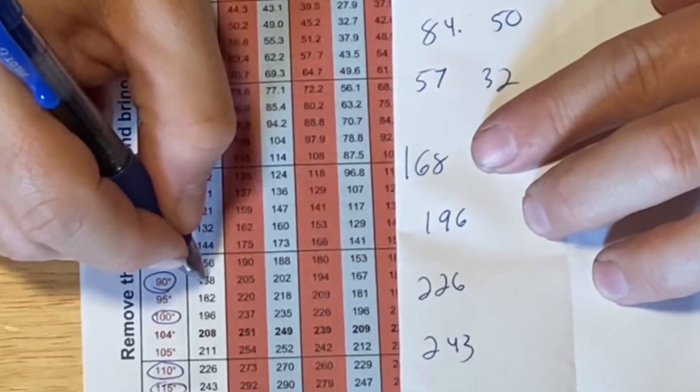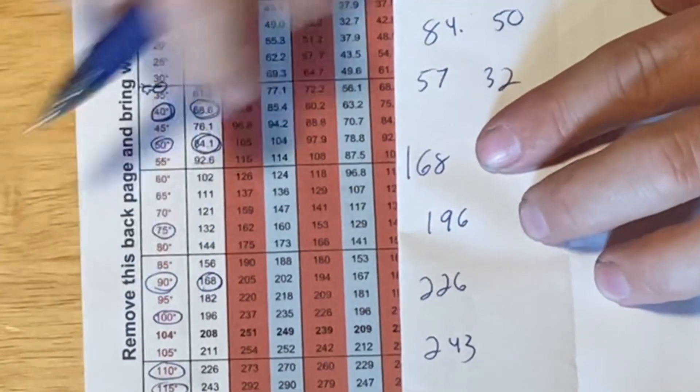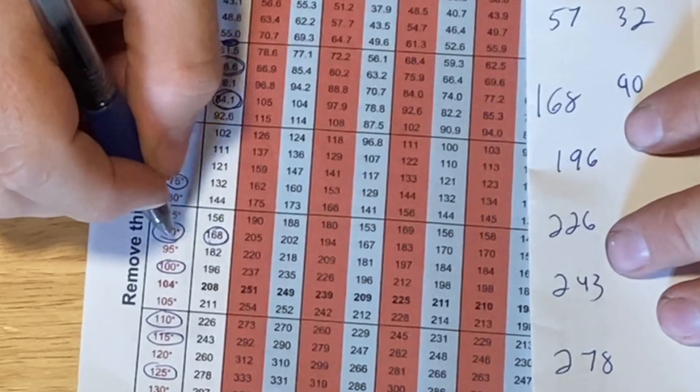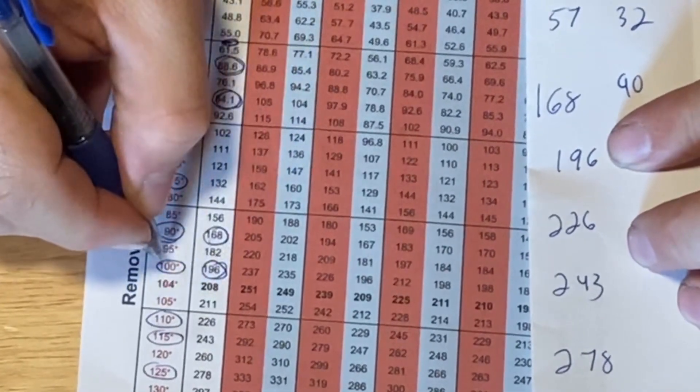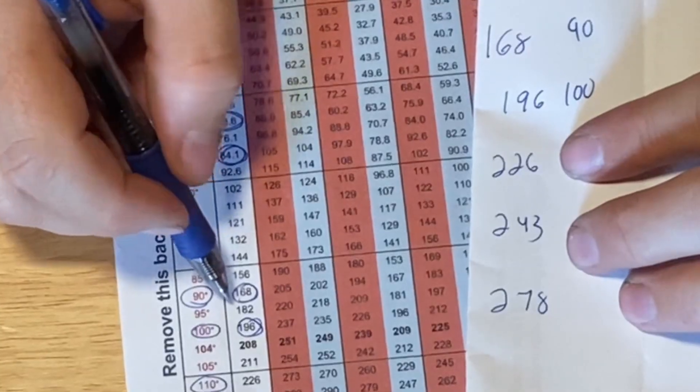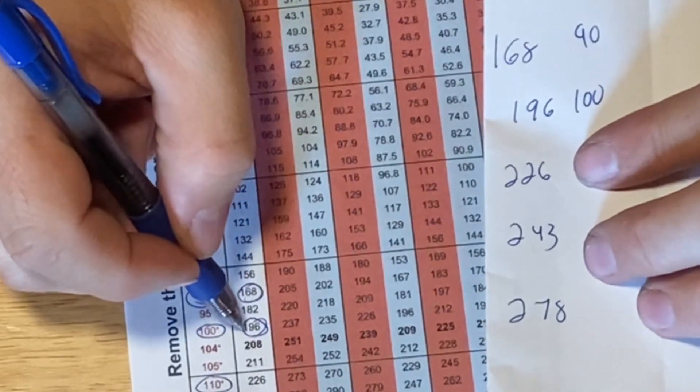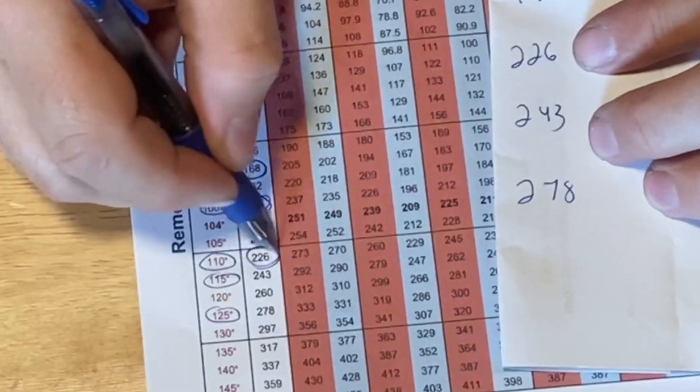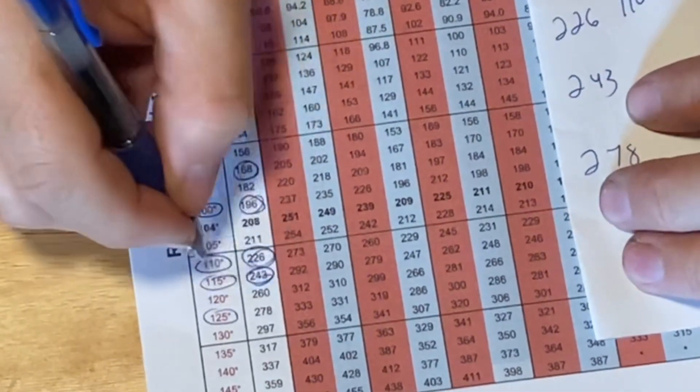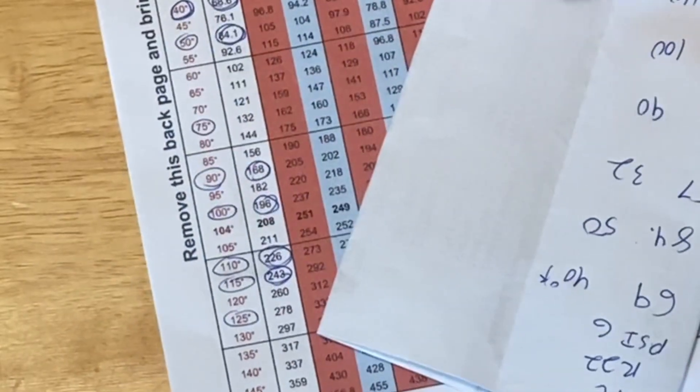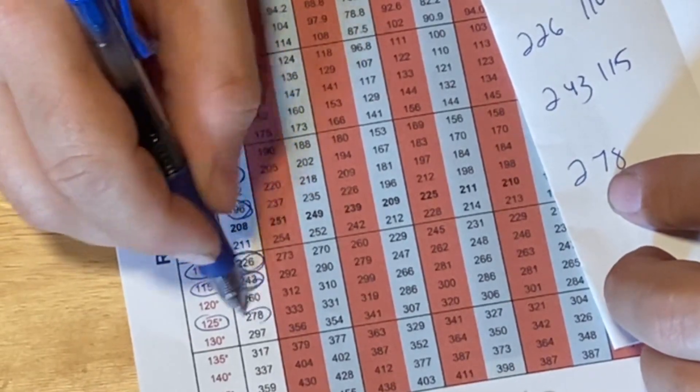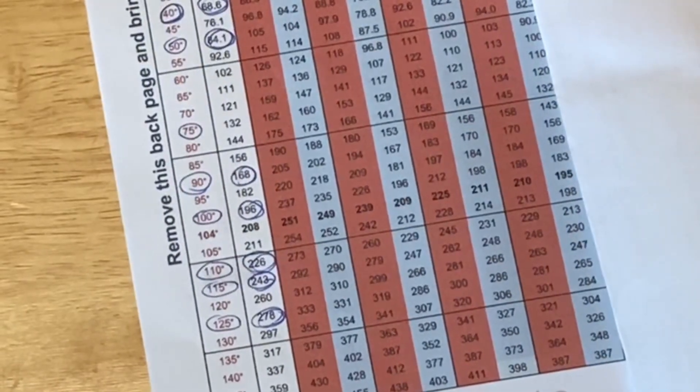Next on the list we have 168. So this could be the high side the red gauge. 168 converts to a saturated temperature of 90 degrees Fahrenheit. 90 would be warmer than the air temperature outside. So we have another temperature of 196. 196 converts to a saturated temperature of 100 degrees Fahrenheit. Now we have 226. That converts to a saturated temperature of 110. And we have 243 converts to a saturated temperature of 115. And then we have our pressure of 278 converts to a saturated temperature of 125 degrees Fahrenheit.